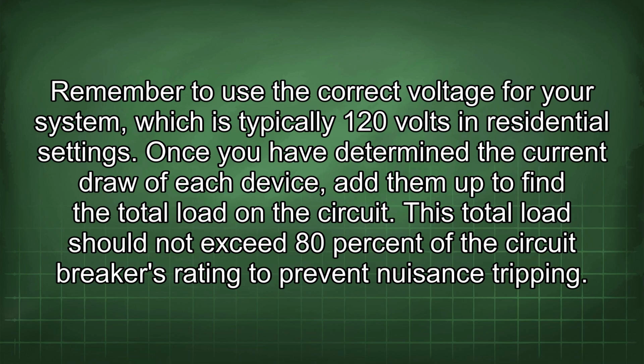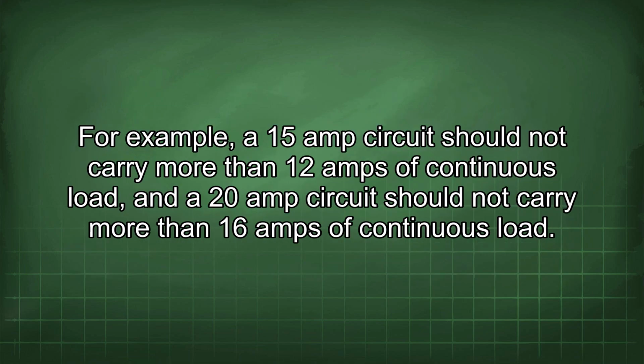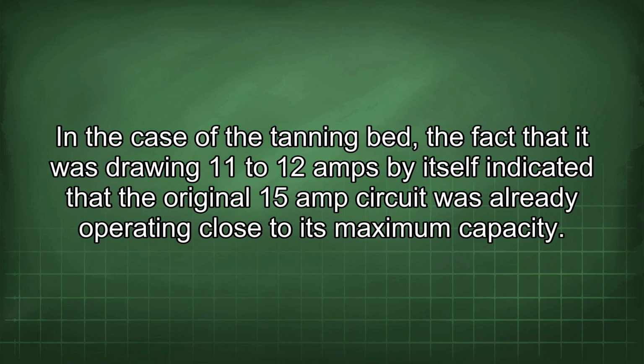Once you have determined the current draw of each device, add them up to find the total load on the circuit. This total load should not exceed 80% of the circuit breaker's rating to prevent nuisance tripping. For example, a 15 amp circuit should not carry more than 12 amps of continuous load, and a 20 amp circuit should not carry more than 16 amps of continuous load. In the case of the tanning bed, the fact that it was drawing 11 to 12 amps by itself indicated that the original 15 amp circuit was already operating close to its maximum capacity.